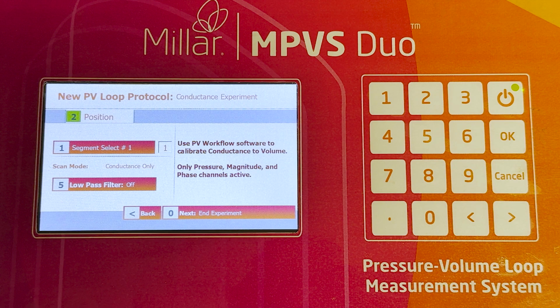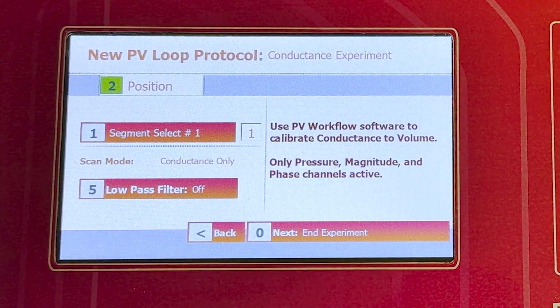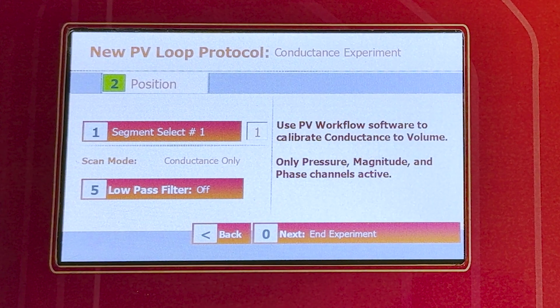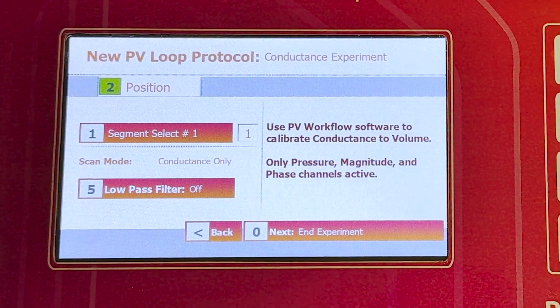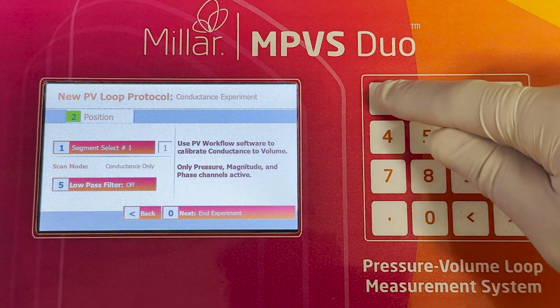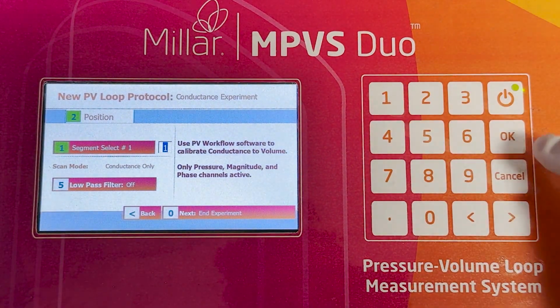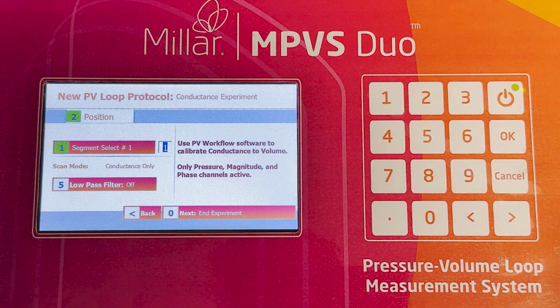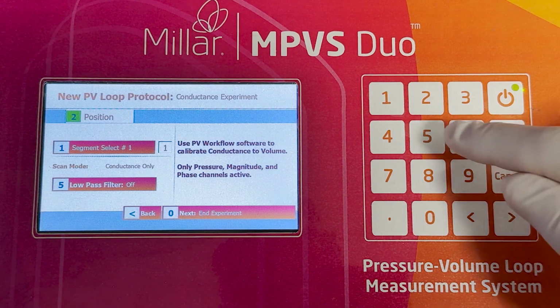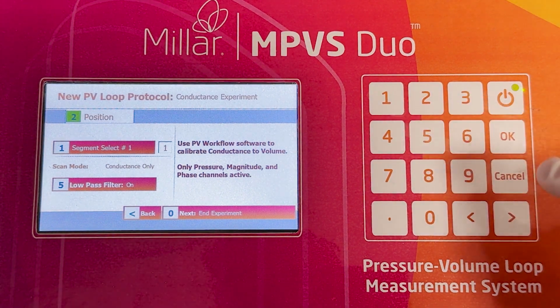Introduce the catheter into the ventricle. For large animal catheters, make sure you select the segment with a size suitable for the animal's ventricle. To do this, press 1 and then the segment number and OK to select. Please see the manual for more information on the segments and their lengths. Segment length can be changed while the catheter is in the ventricle. A low-pass filter can also be switched on or off in the screen by pressing 5.